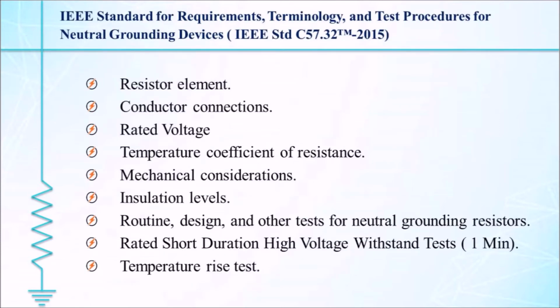This slide is of the IEEE standard for requirements, terminology and test procedures for neutral grounding devices. IEEE standard C57.32-2015. These standards apply to devices used for the purpose of controlling the ground current or the potentials to ground of an alternating current system. These devices are grounding transformers, ground fault neutralizers, resistors and reactors.